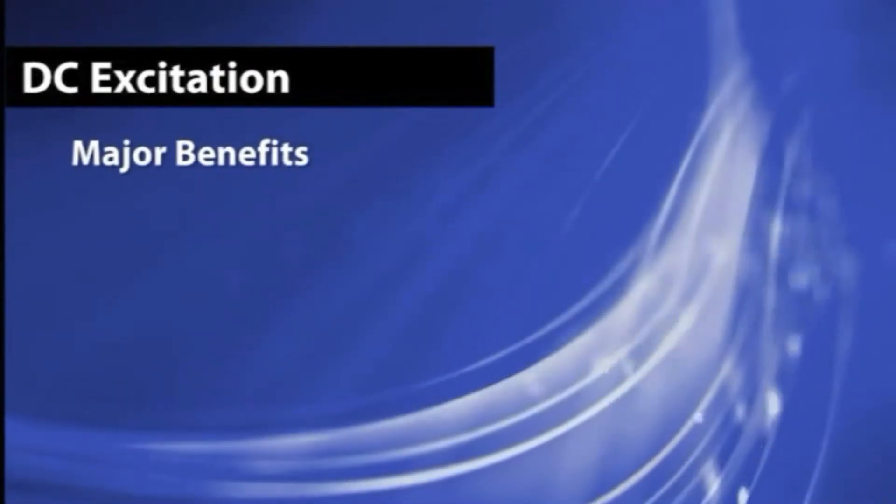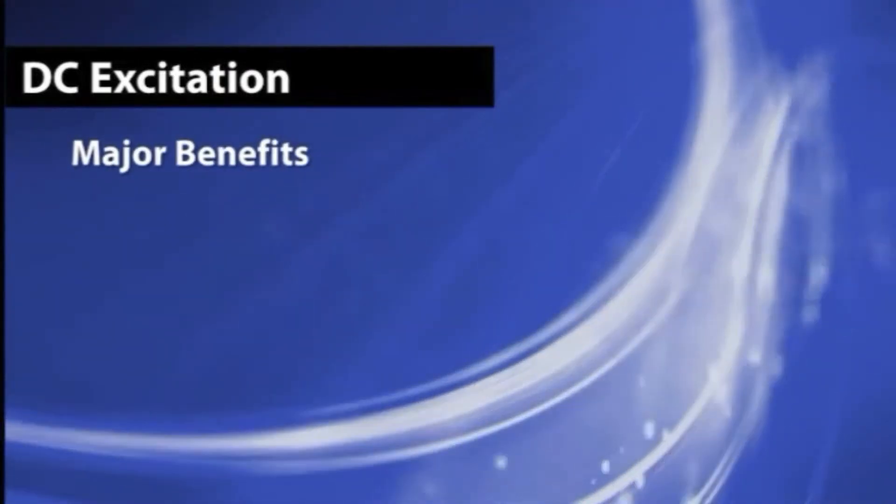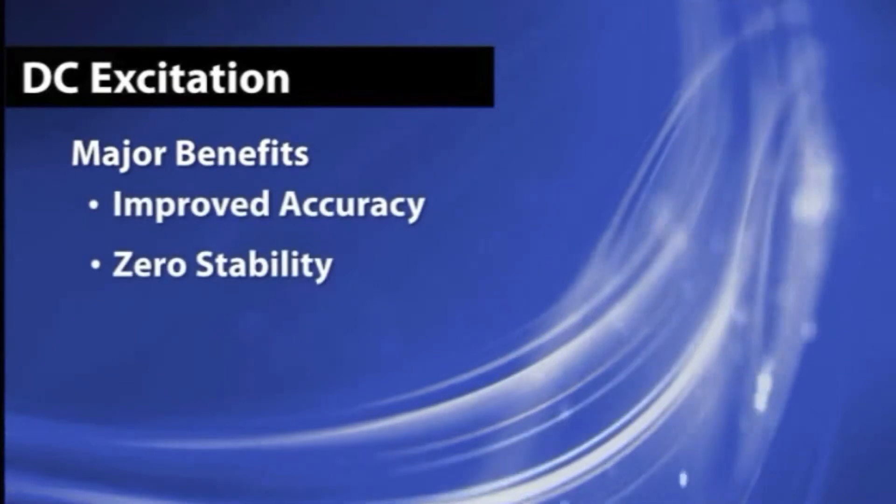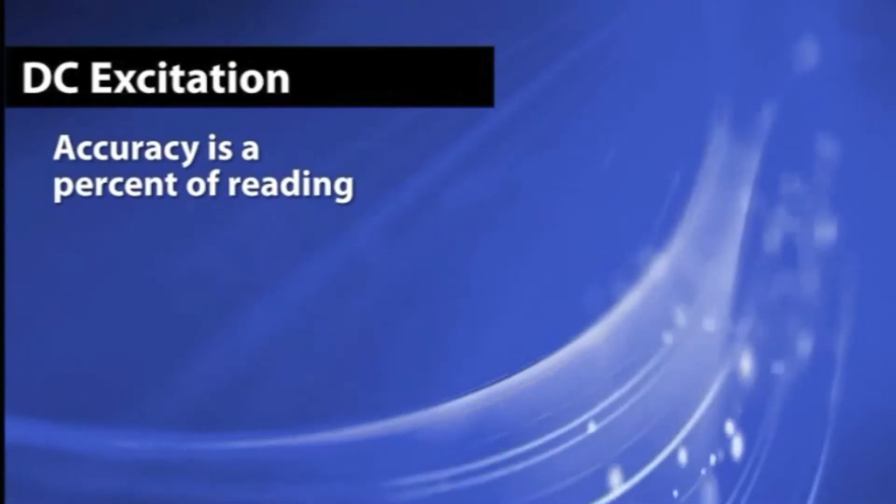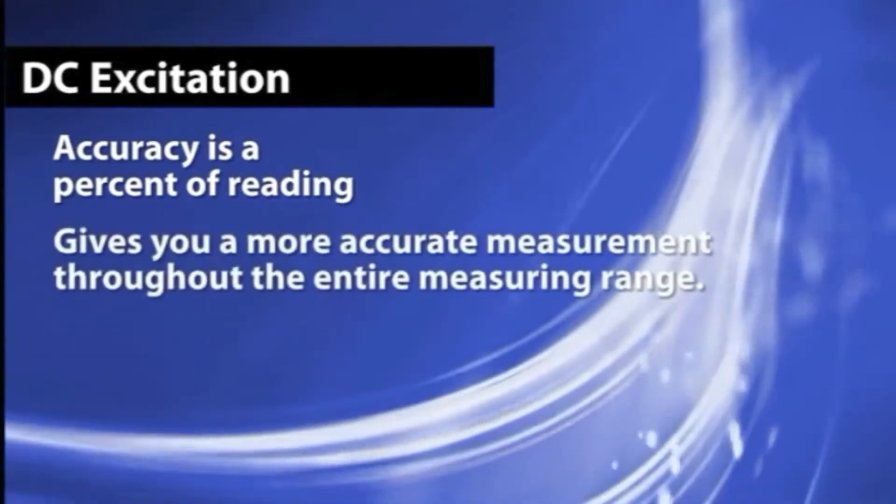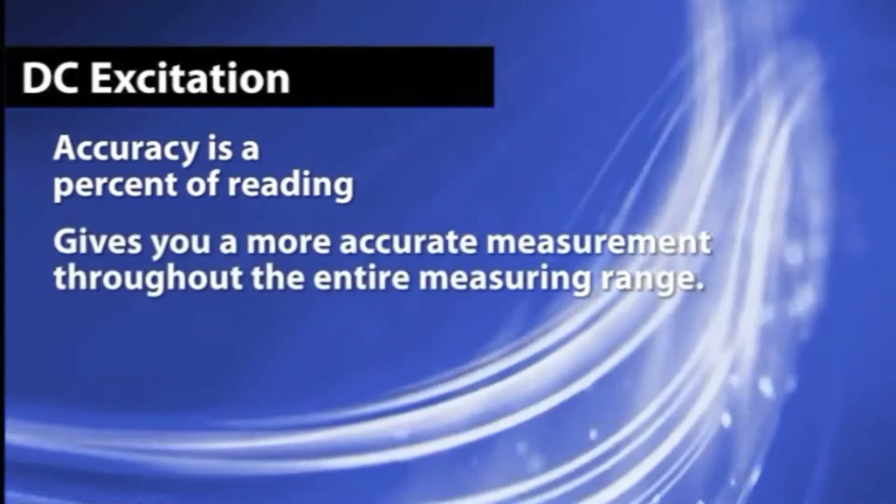The major benefits of pulsed DC excitation over AC excitation is the improved accuracy and zero stability. The accuracy of a DC-type meter is a percent of reading. This gives you a more accurate measurement throughout the entire measuring range.